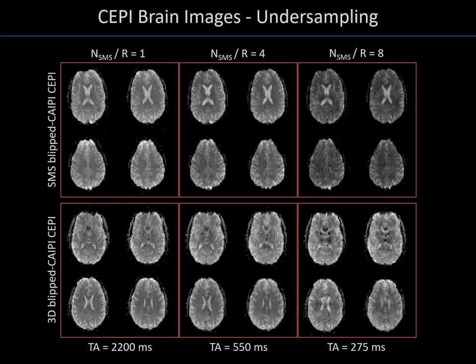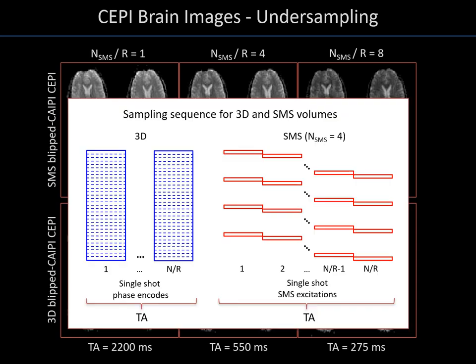One major cause for the loss of SNR at higher acceleration factors in the SMS acquisition is the shorter TR that goes along with it. A quick look at the acquisition timing helps to understand the difference between 3D and SMS sampling. In the case of the 3D acquisition, the entire volume is excited each time, resulting in averaging over the entire acquisition time of the volume. This means that the TR remains unchanged for different acceleration factors, and as a result the SNR of the image is very similar.